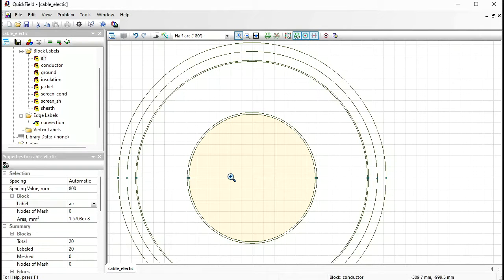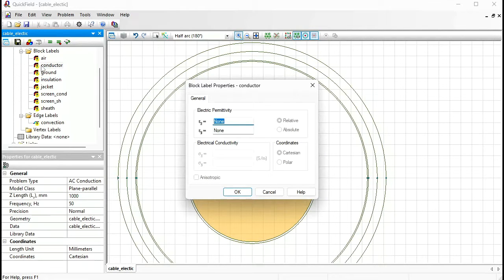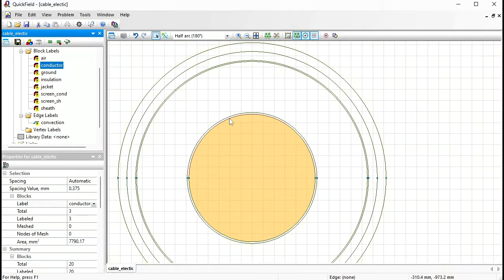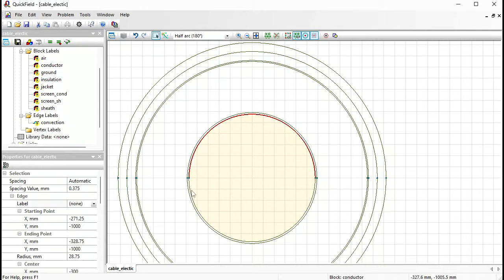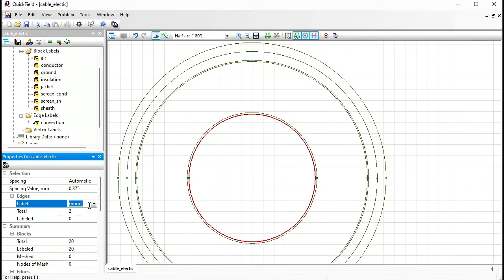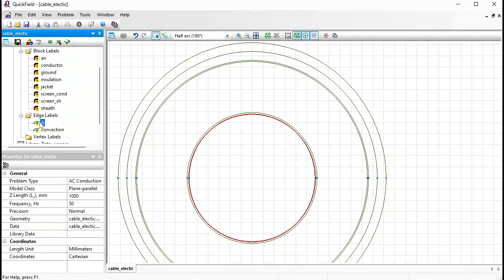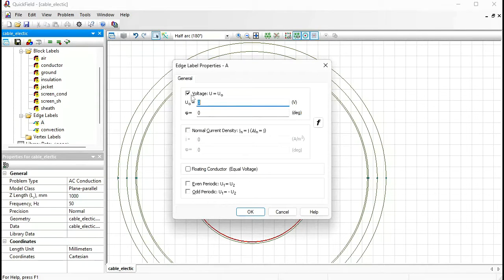I'm going to calculate the electric field distribution. So for the conductor, I didn't specify any properties because there is no electric field inside conductor. Instead, I should specify the electric potential at the conductor surface. So for the conductor surface, I assign label. This is conductor A. And for this label, I specify electric potential. The cable voltage is 400 kilovolts, but in fact, this is the root mean square value. I should specify the magnitude of the sinusoidal wave here, which is times square root of 2 more.